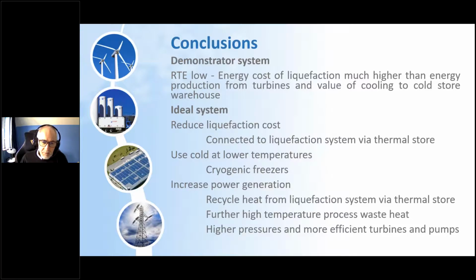But saying that, if you do have a cold store warehouse or a facility where you are using cryogenic freezers — for example maybe using liquid nitrogen to freeze, or CO2 or cascade systems — then there's a much bigger benefit because you're replacing much more energy expensive cooling. So that's also ideal, and if you had the liquefaction system and those cryogenic freezers, you could get even bigger benefits.